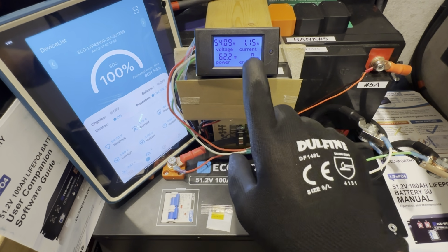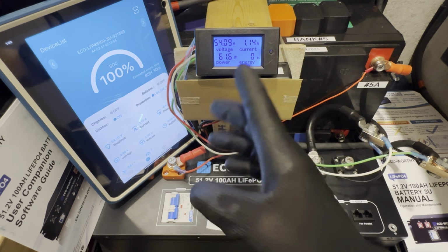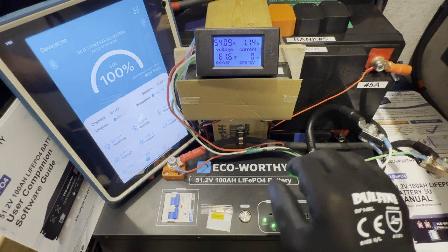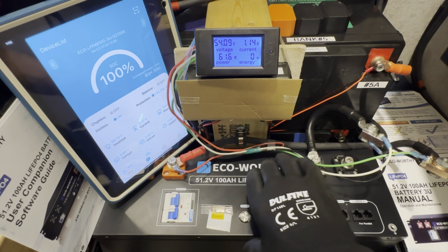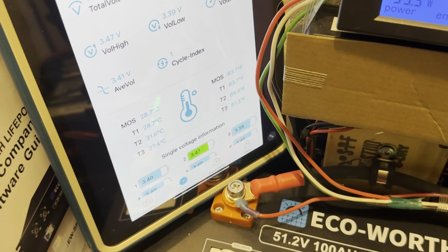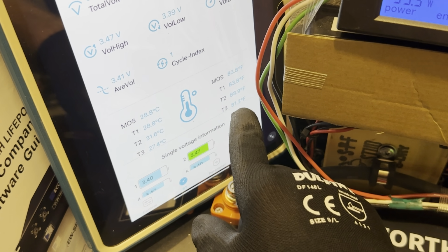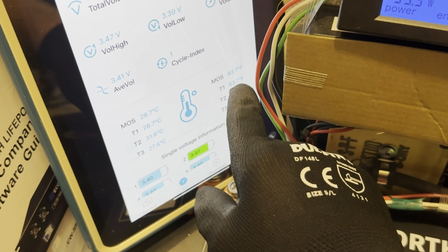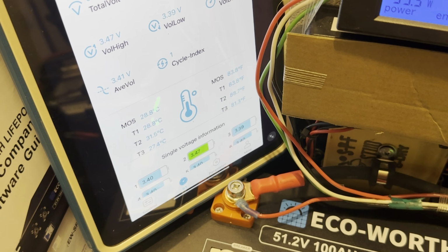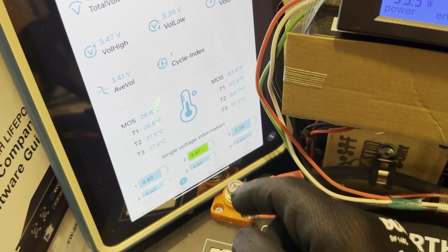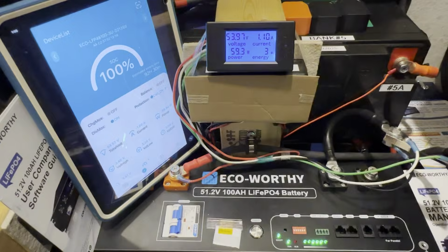So the inverter is on and idling right now, around 60 watts. All PV inputs and everything is turned off. This is just strictly on this single battery right here. And before the test begins, please reference the battery temperatures reported by the BMS right there - 80 plus degrees Fahrenheit for the test.